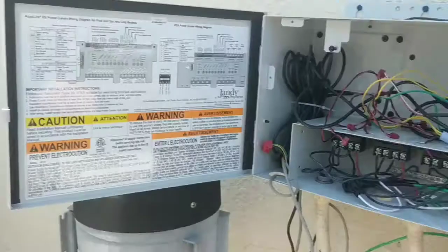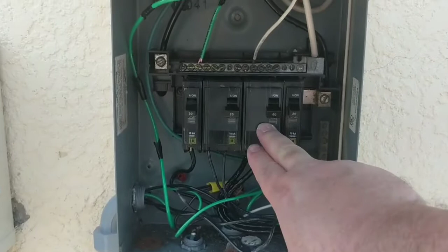As you can see, we have a Hayward heat pump Pro that goes with our pool equipment, and here's the control centers - this is a sub panel. We have a 60 amp breaker in here now. When we started this install, they had a 30 amp breaker in there with 6 gauge wire running to it, to this junction box on the wall behind the heater you see over there. Then they had 10 gauge wire, so 6 gauge met 10 gauge, running to the actual transformer inside the pool heater here inside the box.